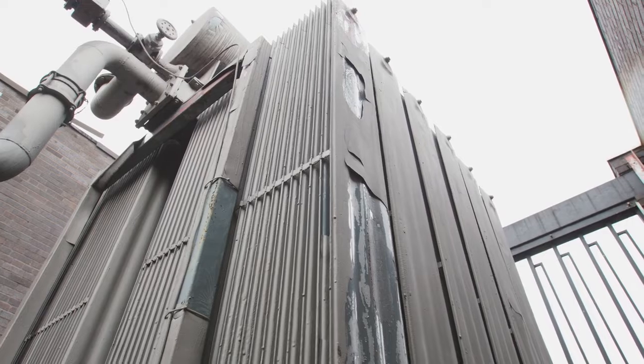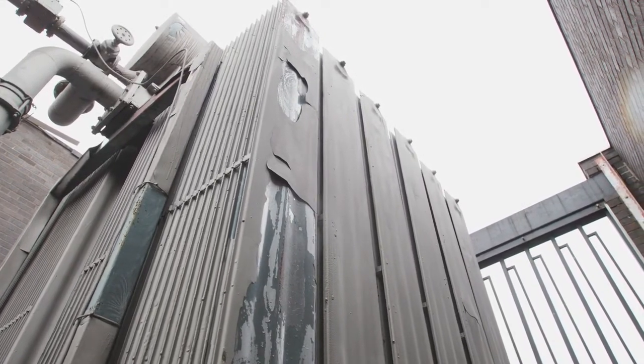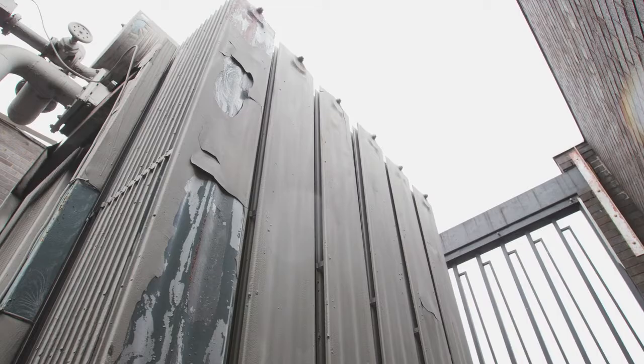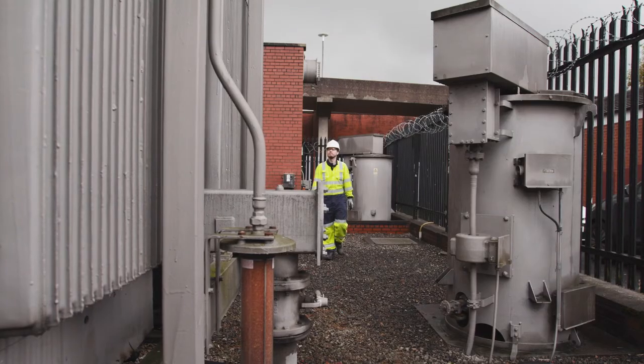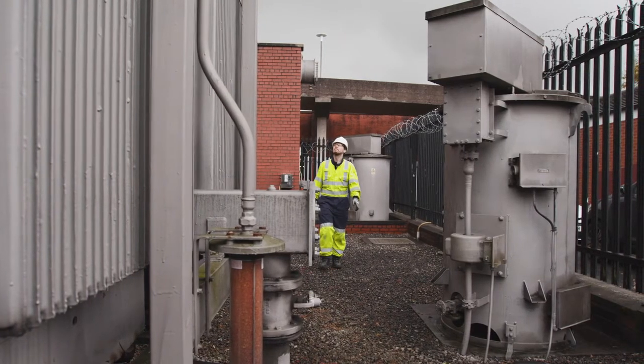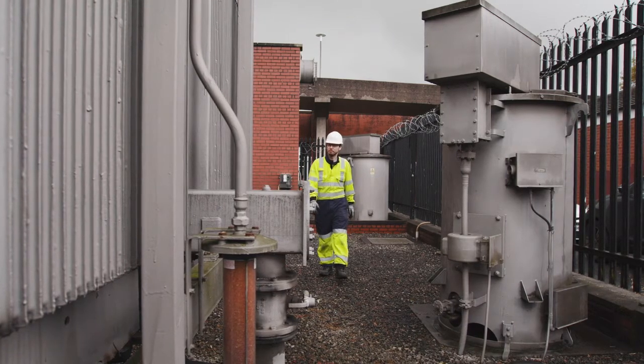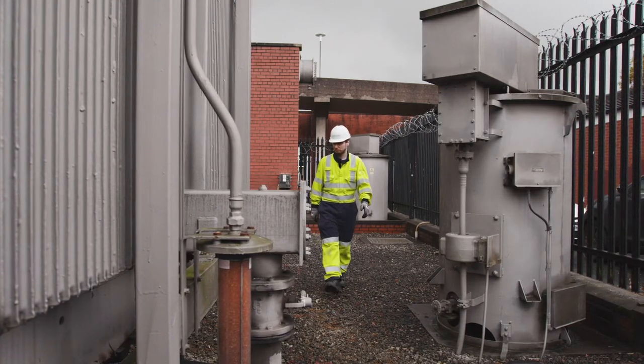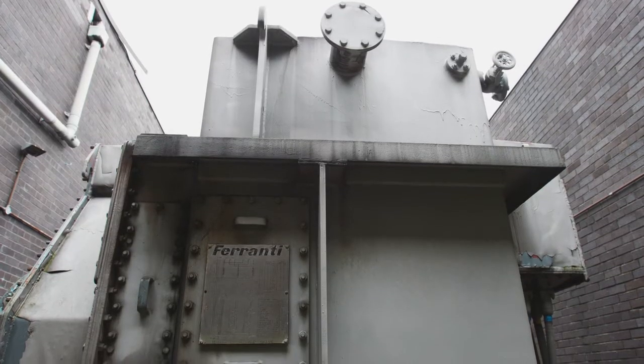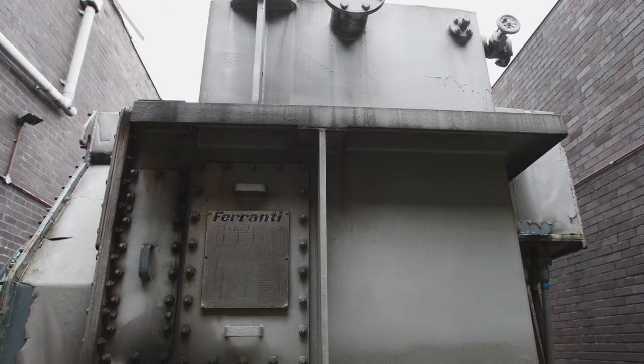So the oil regeneration process that Electricity North West are investigating started life towards the end of the transformer life, where we attached a mobile unit to the transformer, circulated the oil through it using various filters to remove the impurities, and then circulated it back into the transformer. We've since developed that process to a two-stage process now, where we do an initial clean of the oil, and then we found that by heating the unit above 65 degrees, that allows the impurities that are absorbed into the papers that insulate the transformer core to be released. And then we do a second cleaning process which removes those impurities as well.